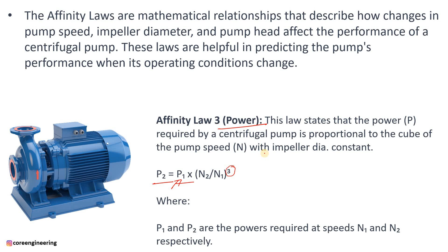What is the relationship between the RPM and diameter with power consumption? Power consumption is P2 is equal to P1 into N2 divided by N1, power 3. It means your new power will be 8 times the P1, the initial power, if you double the RPM. Please understand this. Now, let's suppose the initial power is 10 kilowatt at the initial RPM, for example 100 RPM. N2 is 200 RPM. At N2, what will be the power consumption? Because this is also very important. It would be 10 into 200 by 100, power 3, right? So 2 power 3 is 8, into 10 means 80 kilowatt. So your power will increase 8 times. The new power will be 8 times your initial power, right?